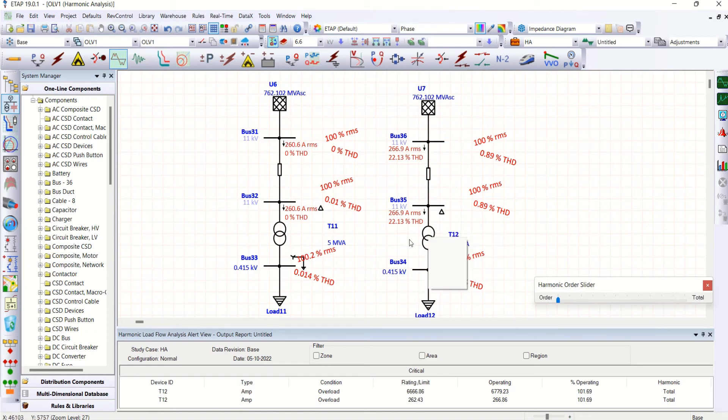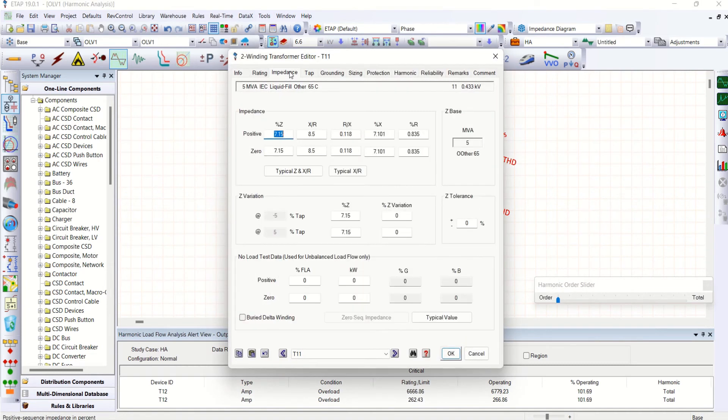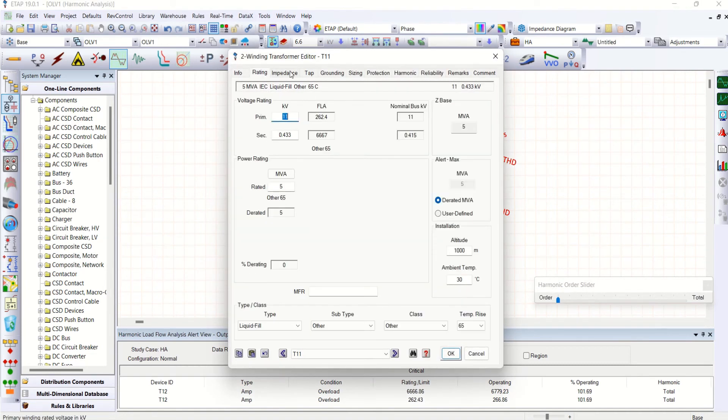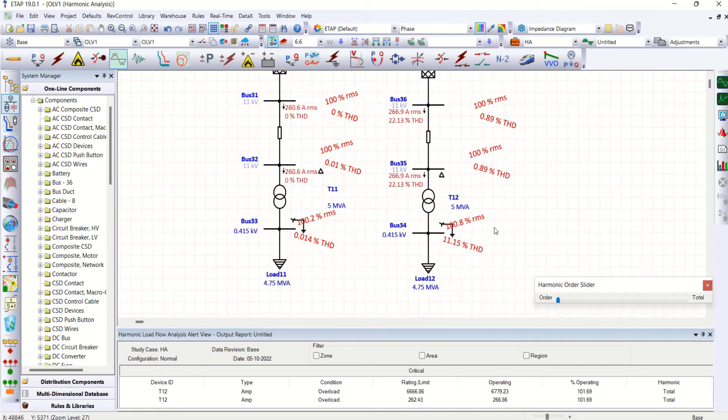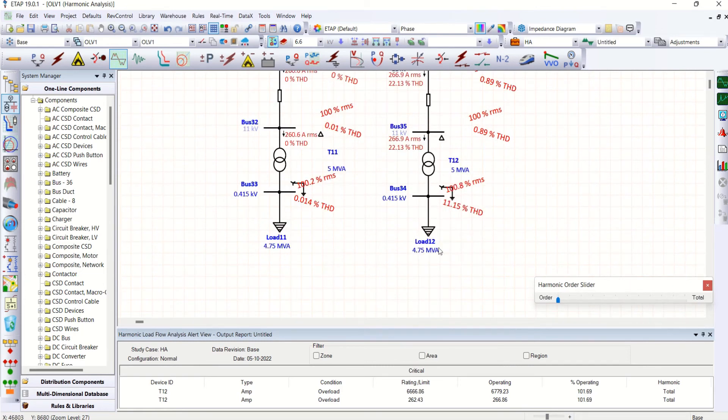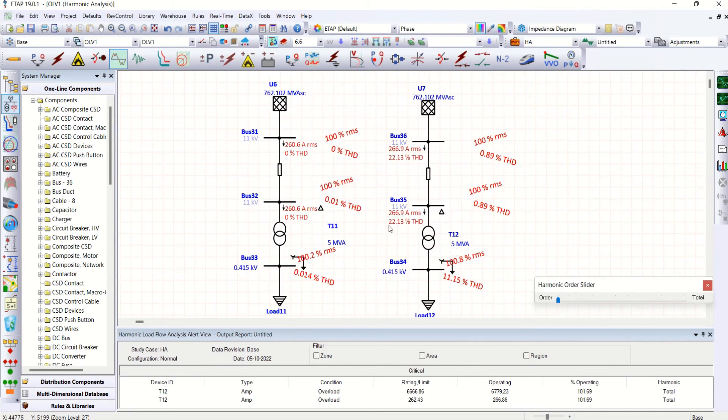So whereas in the previous case, even you could have seen on the transformer, the transformer is on the rating page, you can see 262 is the full load current. Whereas here 260.6 is maintained, but with the harmonic load, same, you could see same load 4.75. Nothing has been changed.